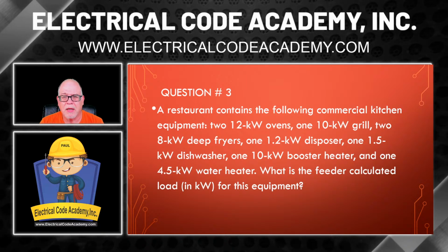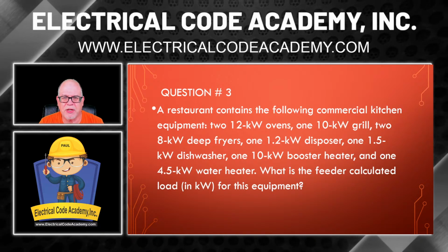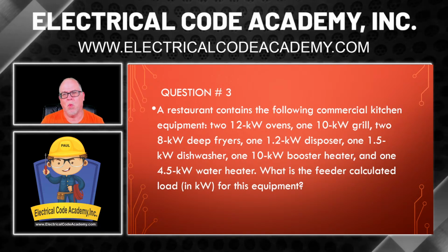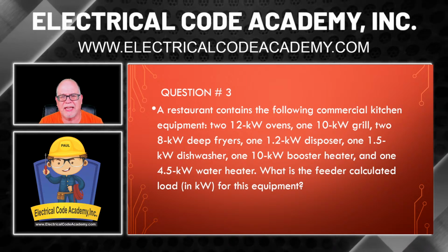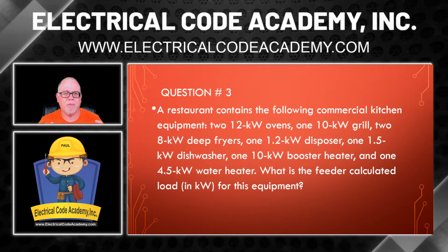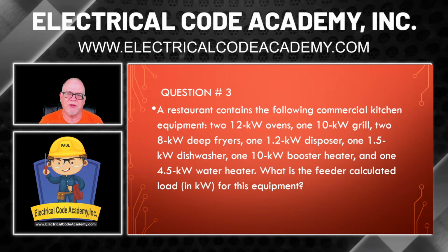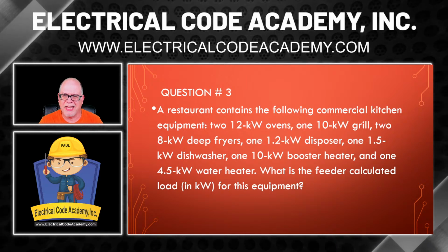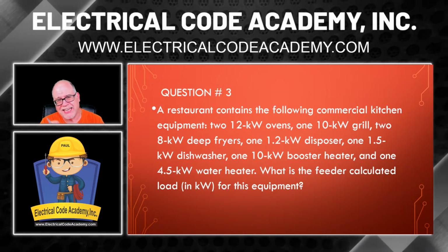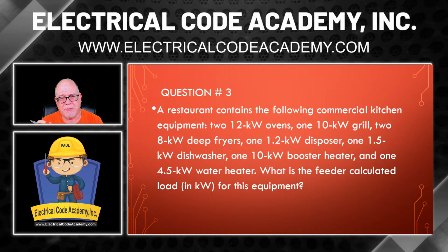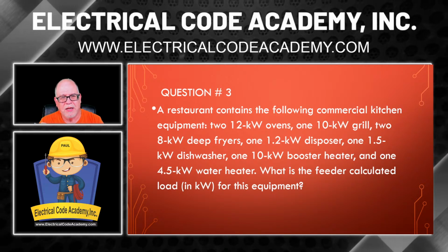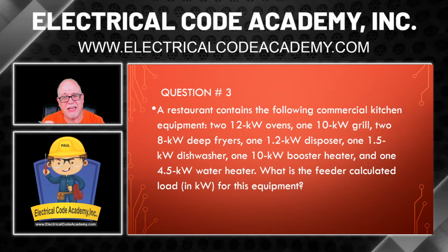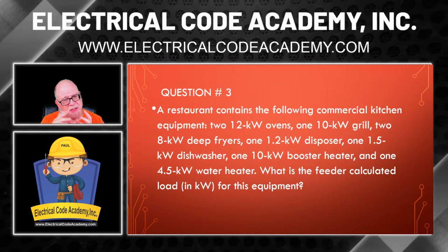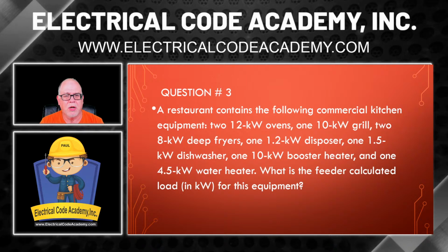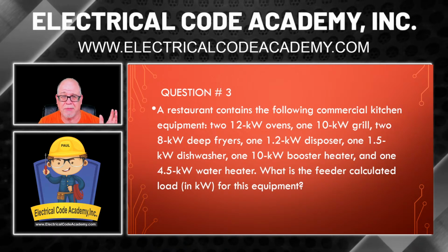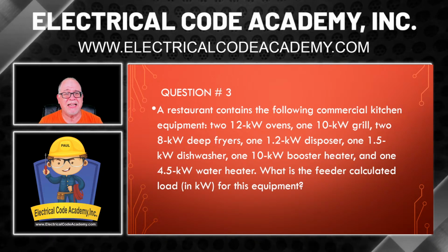Each one of them has a kW value. The last part of this question wants to know, what is the feeder calculated load in kW for this equipment? Now, remember different terminologies, and we've covered this in other videos. You have what's called a connected load, and you have what's called a calculated load. A calculated load is very similar to when they say, what is demand load? It means that you're implying something's getting added to this, or some kind of demand, or something's being done. There's a calculation to take place. Whereas a connected load is simply adding everything up. And that's the first thing that I want to do.